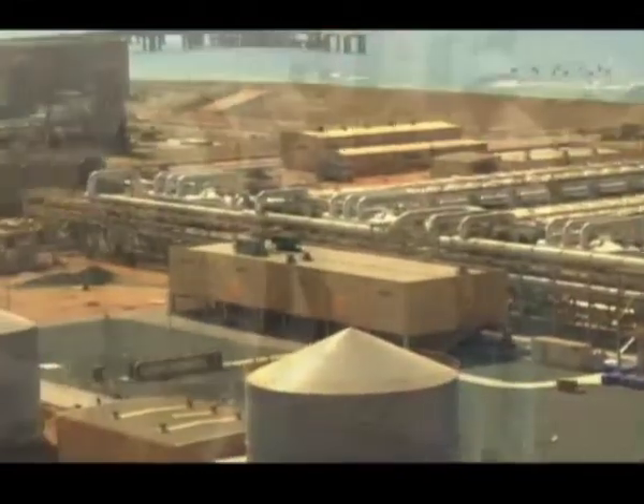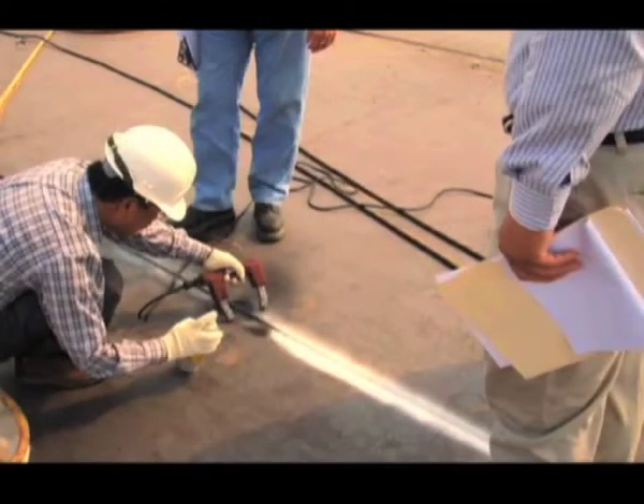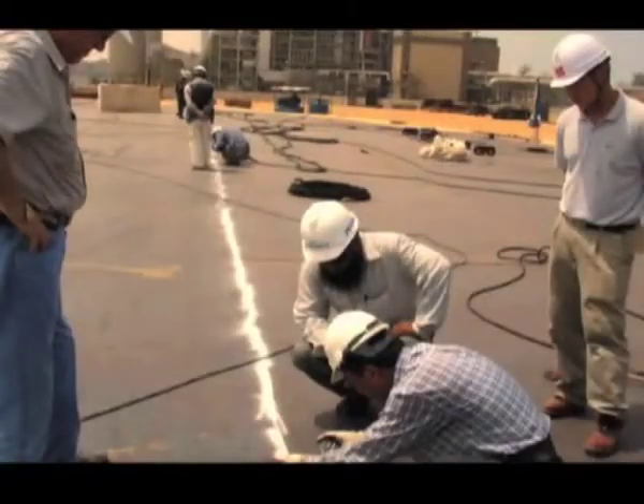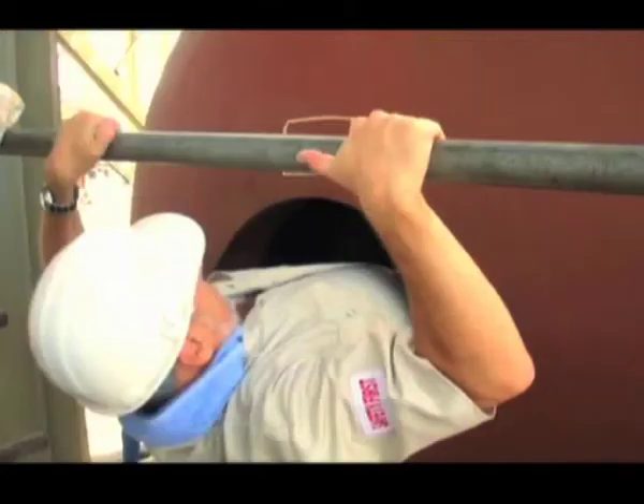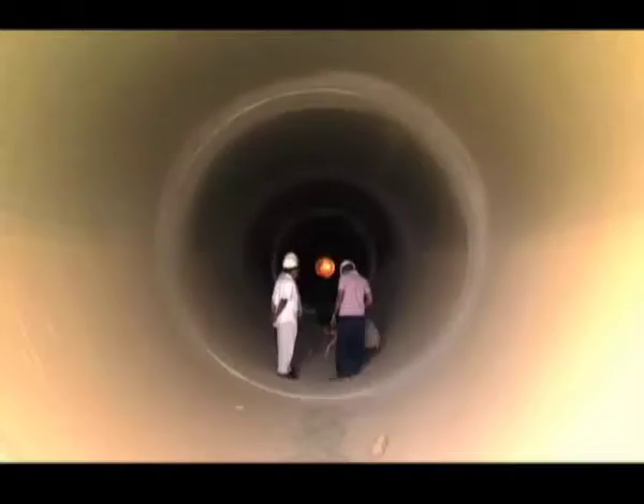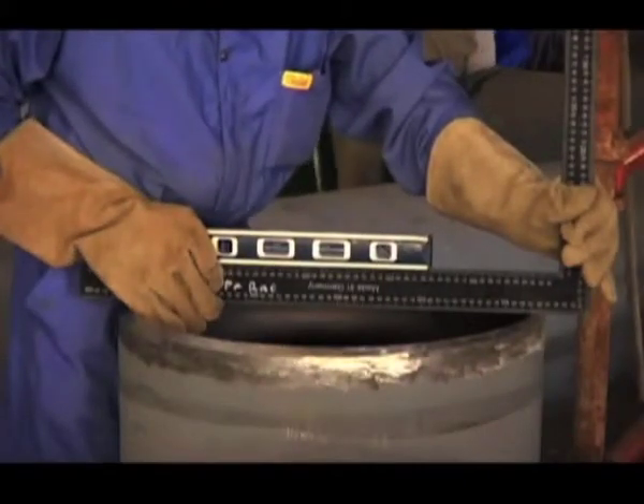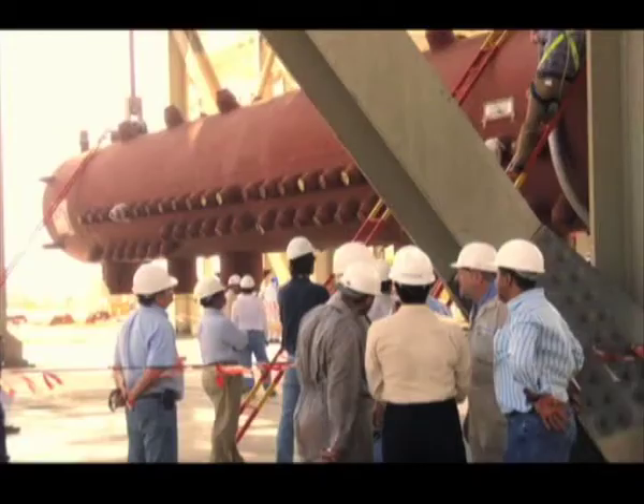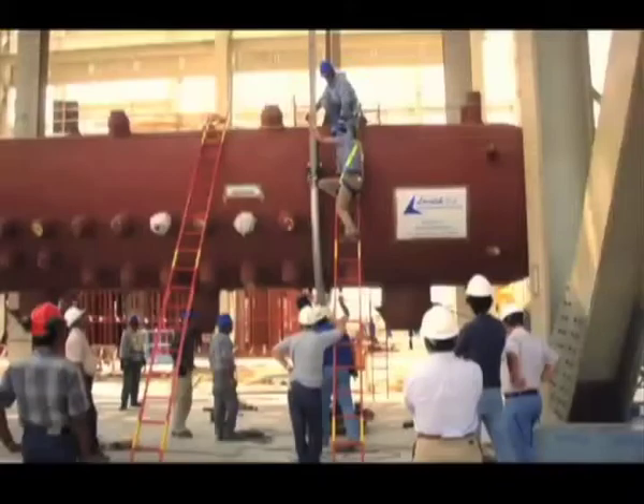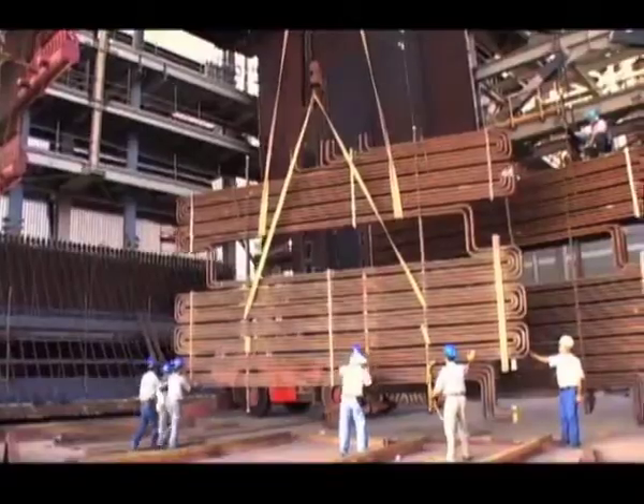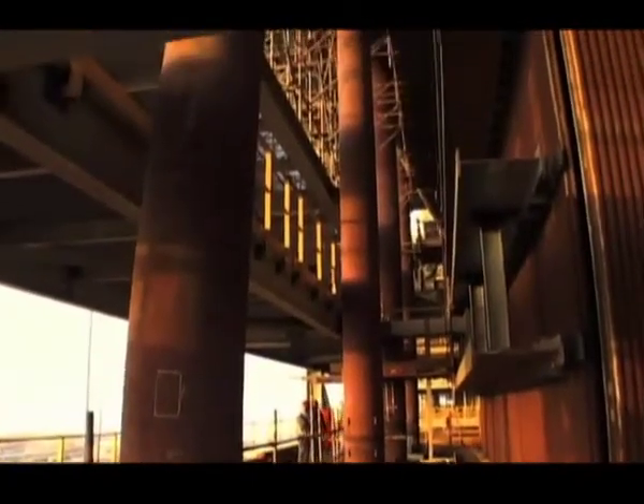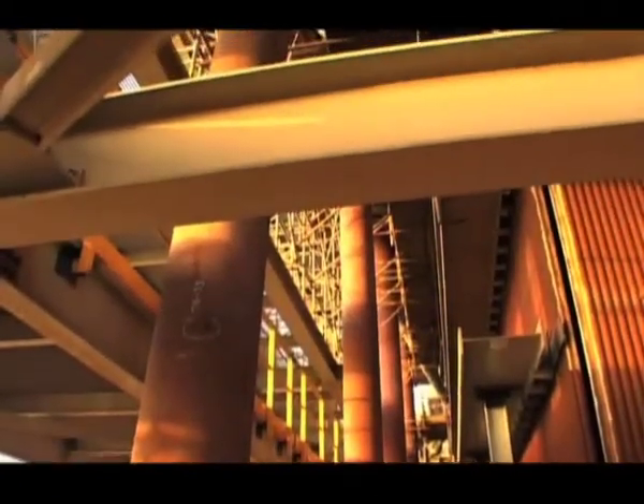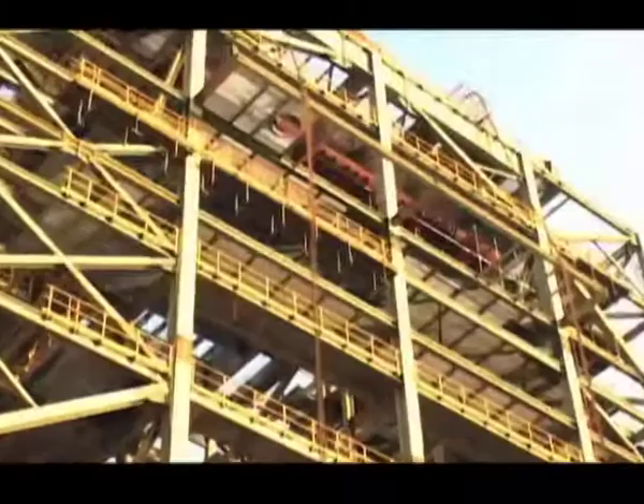Many challenges were associated with the supervision of this complex project, challenges that spread across a number of continents. To avoid potential impact on the erection schedule or the future reliability of the plant, the SWEC project team implemented a project management system using the internationally recognized ISO 9001 as a guideline. A comprehensive, risk-based inspection and audit program was established to maintain constant vigilance of the works. With more than 11,000 welded joints on each unit connecting the boiler drums to associated piping works, it was paramount that a high quality of works be maintained to ensure success of the project.